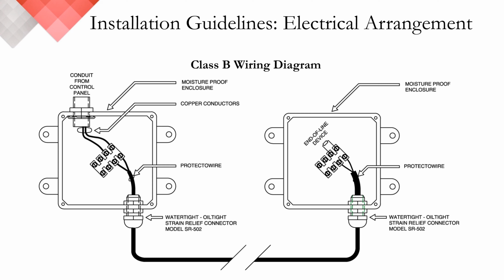For all detectors, the appropriate feed cable is brought into the junction box at the start point of your zone. Feed cable is landed in the appropriate terminal block. For PHSC and PLR, it doesn't really matter which post you use since we're not really concerned about polarity. But for CTI, we must pay attention to polarity and be sure that we're actually connecting the copper conductor with the copper post in the terminal block and the constantan to the constantan post in the terminal block, which are color-coded so it's easy to identify.